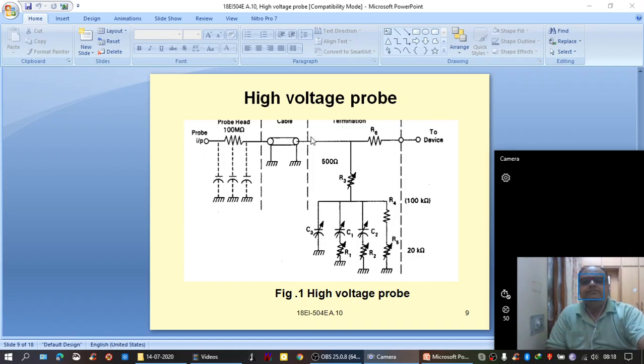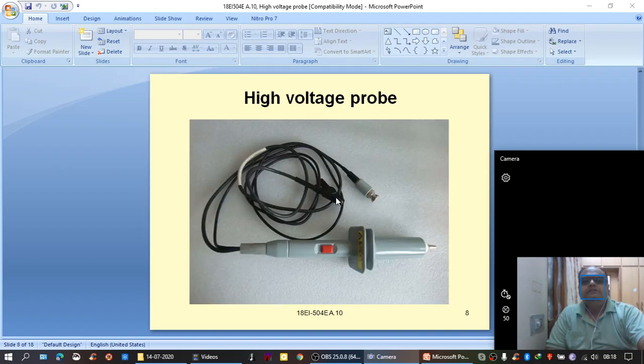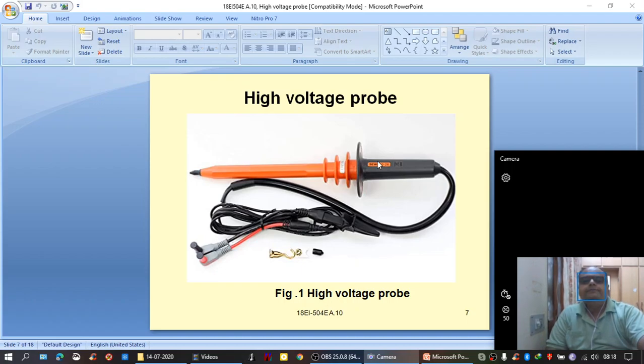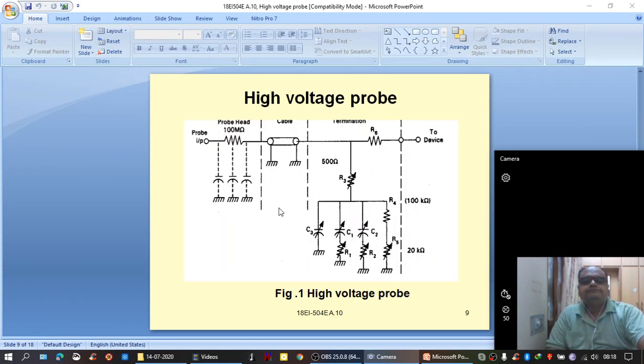It has been shown as a separate part, but actually after probe head comes the cable, then comes the termination. This is probe head, this is cable, this is the terminating portion. Probe head, up to here cable, this is the termination portion. And in the termination portion, this is the circuit used for this stray capacitance loss and a current limiting resistor connected to the device. A voltmeter, a normal voltmeter can be connected here.